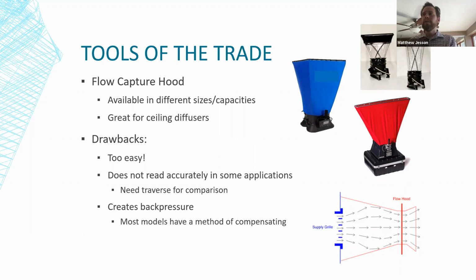It doesn't read accurately in some applications. You might need to take a duct traverse for comparison. And finally, it creates back pressure. If you kind of take a look at the bottom right here, what the hood does is the airflow comes out of your grill, it spreads out, it hits the sides of the hood, the fabric, and it kind of washes against that. And the hood directs it down through the measurement device.